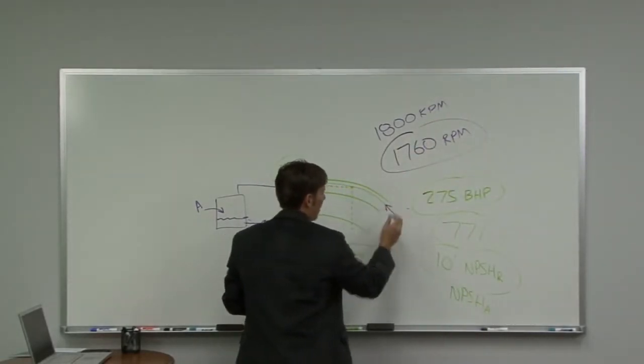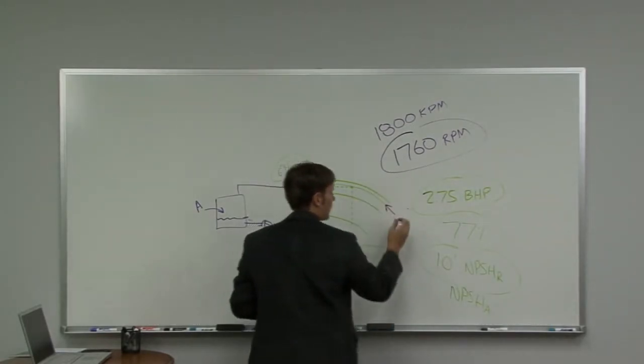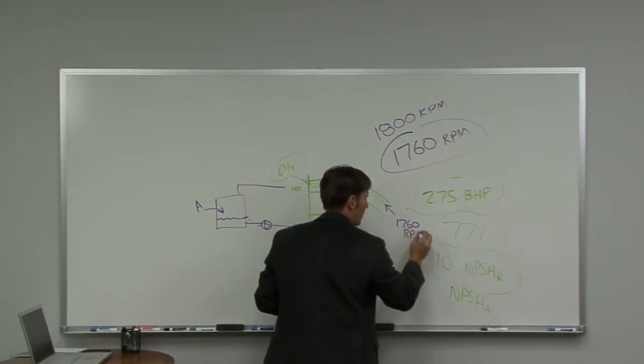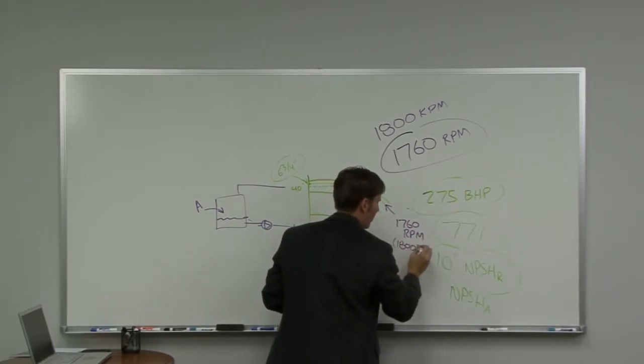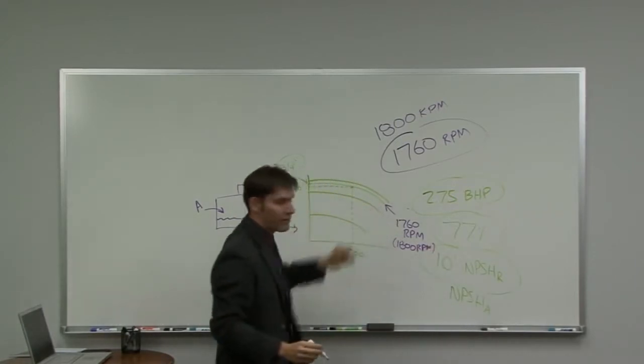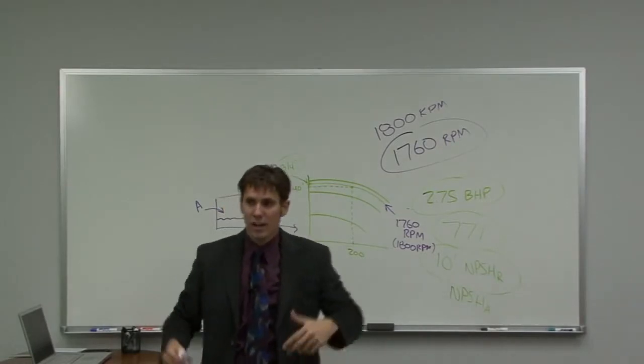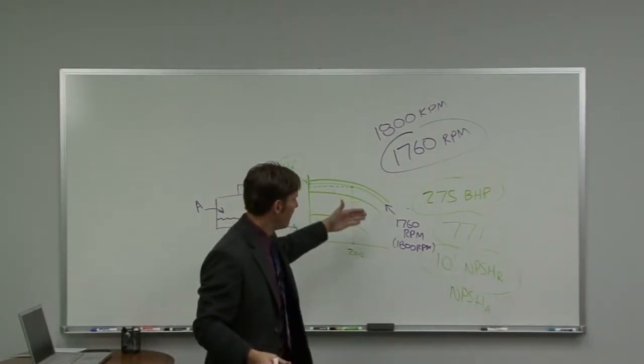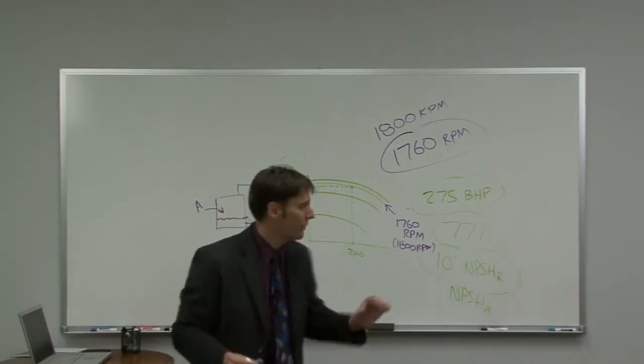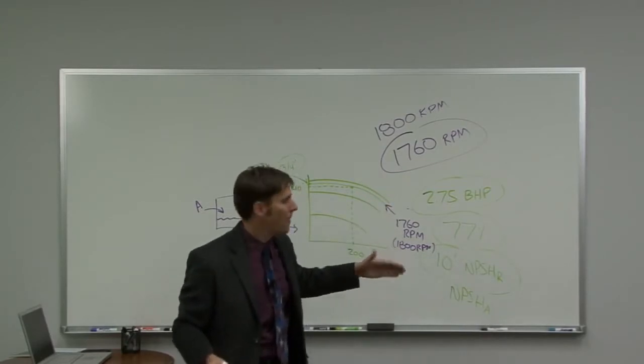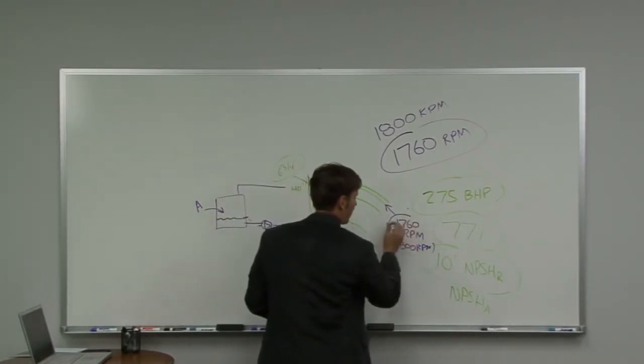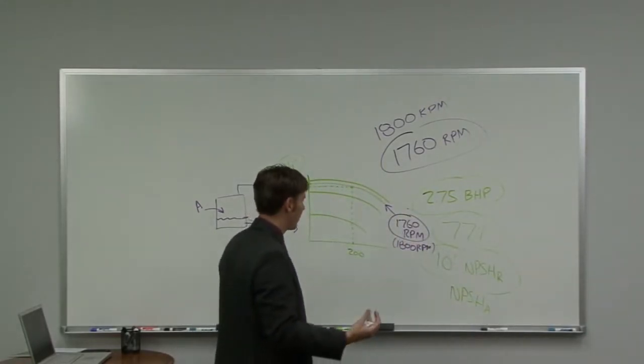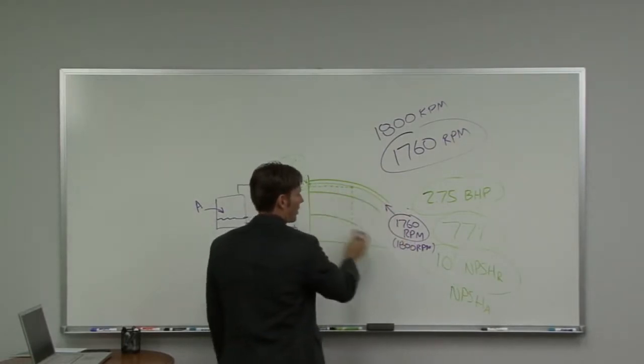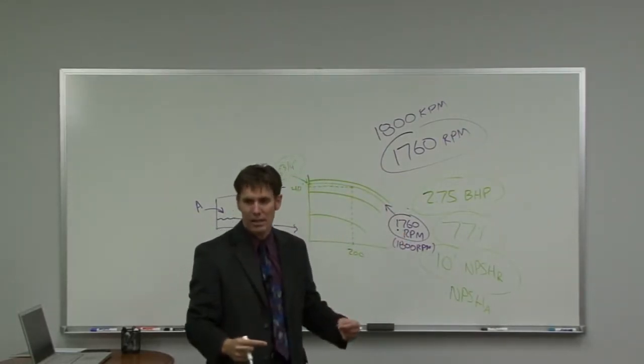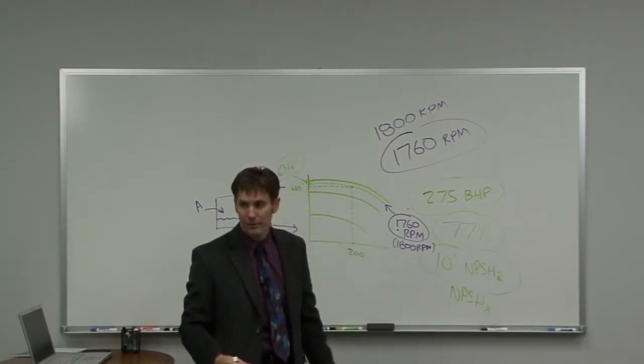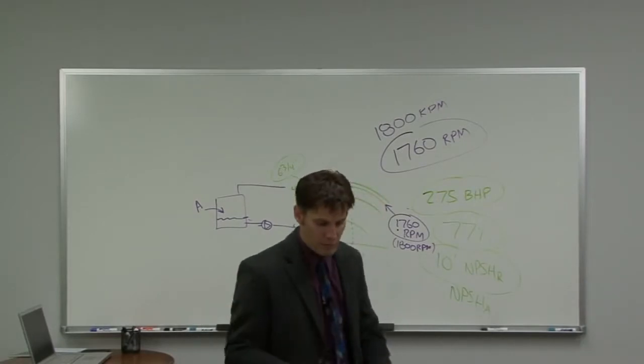So on this pump curve, my pump will operate like this as long as I'm rotating at 1760 RPM with the 1800 RPM motor. Now you put a premium efficient motor on there, and you won't be operating quite there anymore. It's going to be a little bit more efficient because you've got a premium efficient motor. If you have a standard efficiency motor, then it might be here. So again, this is not an exact science what they've done. They're not giving you all of the variables in this pump curve. But what we need to understand is this will be the minimum based on that standard efficiency or the EPACT efficiency motors, and then we will operate on this curve as long as we are rotating at that given speed. If my speed changes, so does my curve.